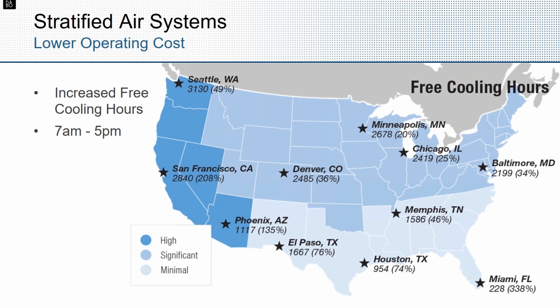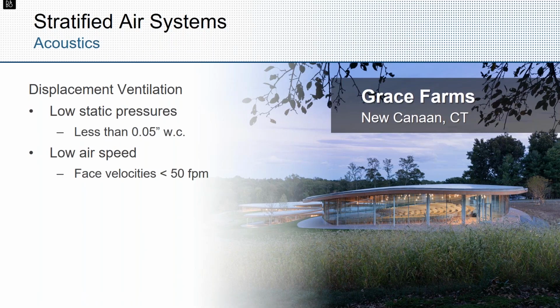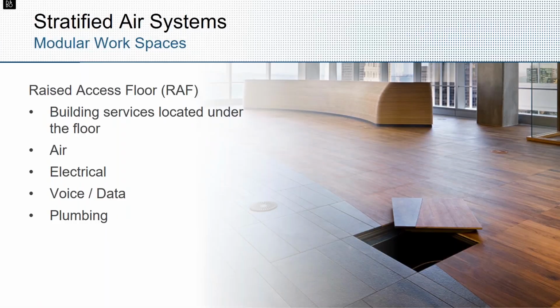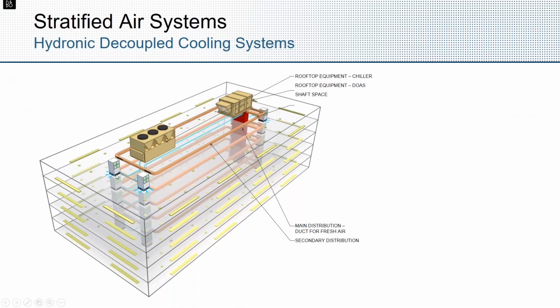Oh, I see. Yeah, so I was mentioning you can really minimize the amount of ductwork with the UFAD system. We're starting to see a lot of this type of design where you've got a vertical discharge unit at each corner of the building, which really minimizes the path or length the air has to travel underneath the floor.